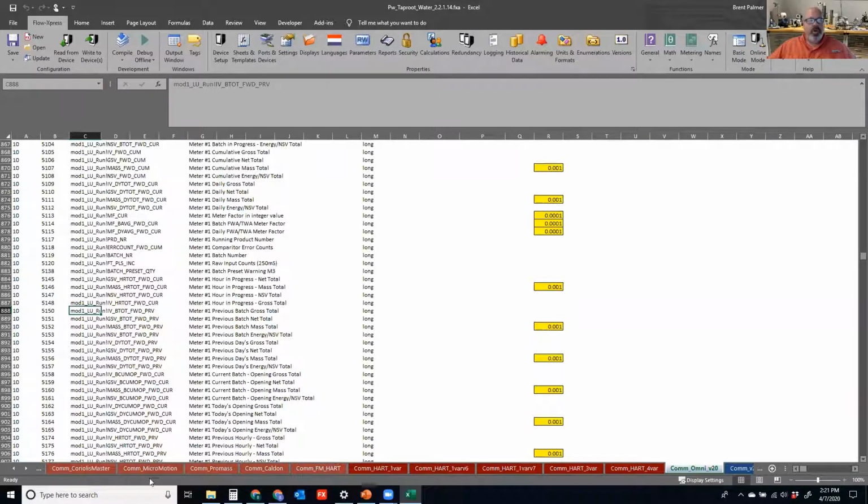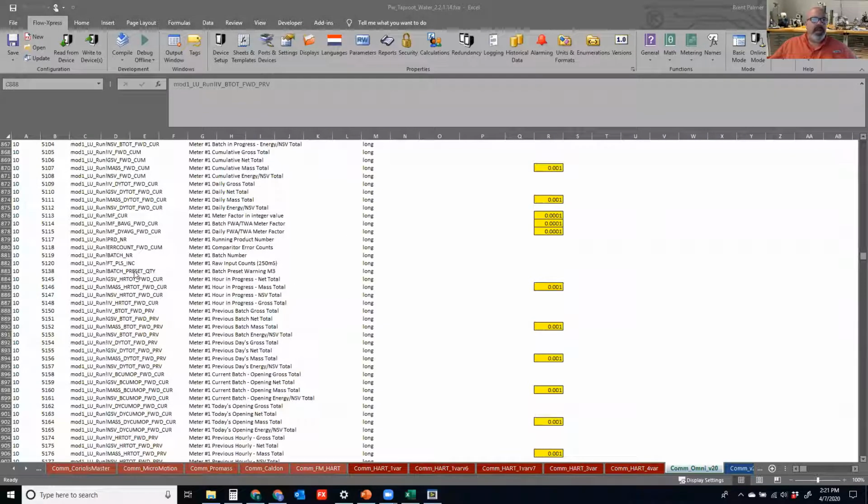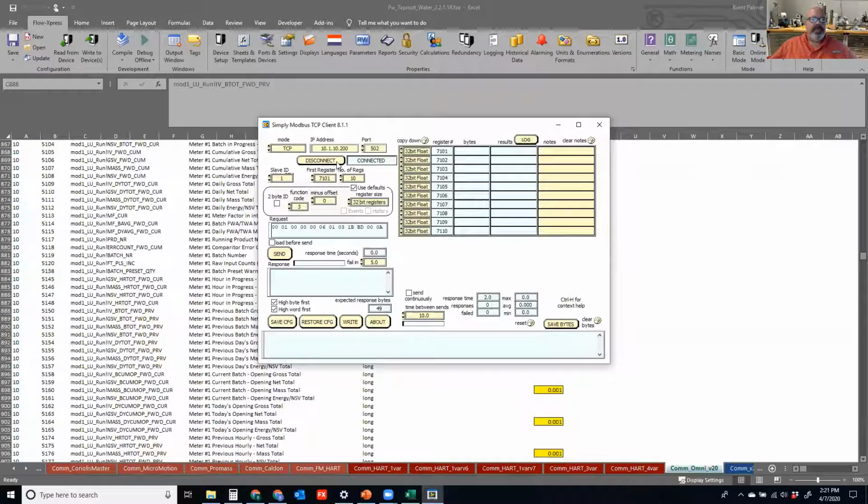So instead of having to open up a Modbus poller and then try to connect into a device, we'll disconnect, we'll connect in, and then I want to poll these registers. We said 5101. I'm going to poll them, and they are 32-bit registers, but they're integers. They're not floats, so I have to make sure I know that they're that way. Then I hit send, and that's great. I've got data. But what's the data? Well, it's 1028, it's 4398, but what does that data actually mean?